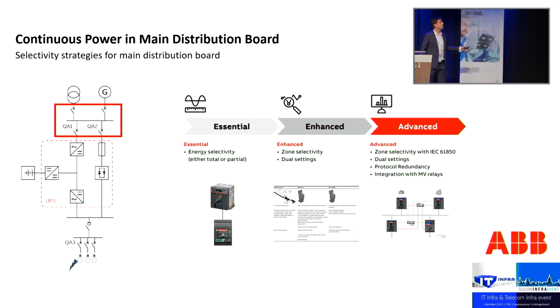So I need to go to different strategies, what we call enhanced and advanced selectivity, and I need to use digital-based selectivity, communication between the protection devices, in order to send signals to identify where the fault is and which device should trip. Maybe I didn't mention the main reason or main strategy of the selectivity. I want to minimize as much as possible the part of the system which is influenced by the fault. So I want to have the isolation of the smallest portion of the system where the fault is. So for me, it's easier to clear the fault. And of course, I have much less impact on the installation.